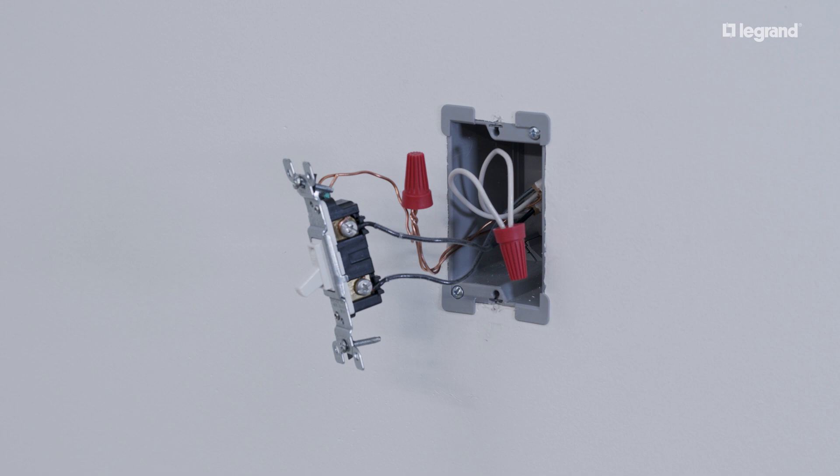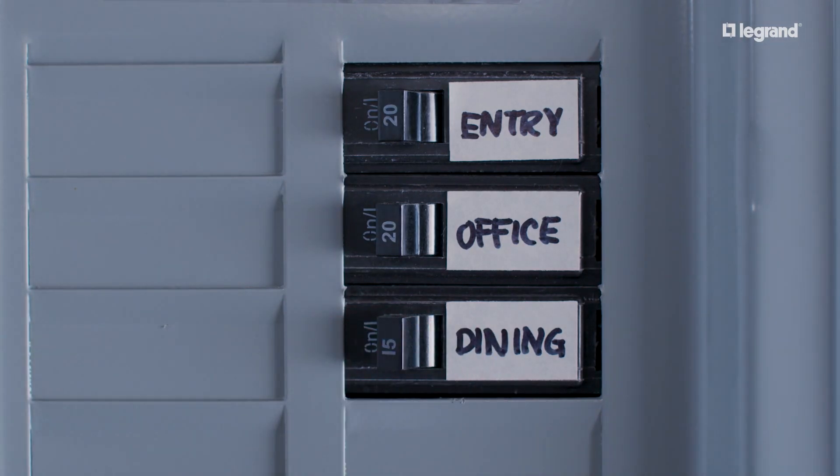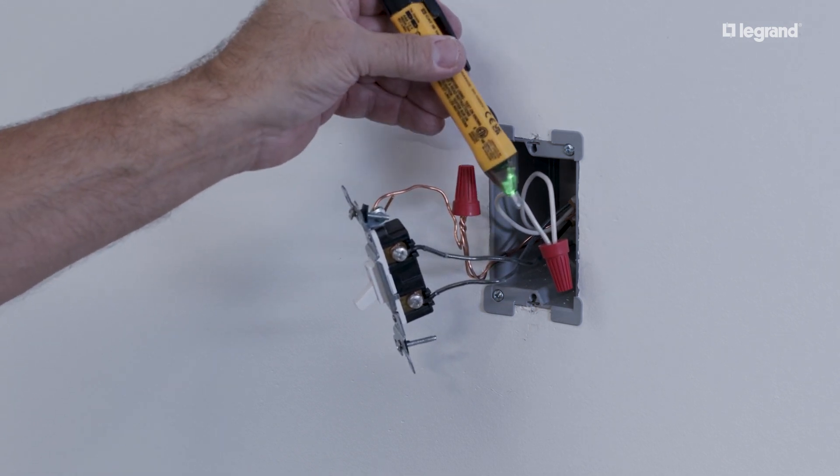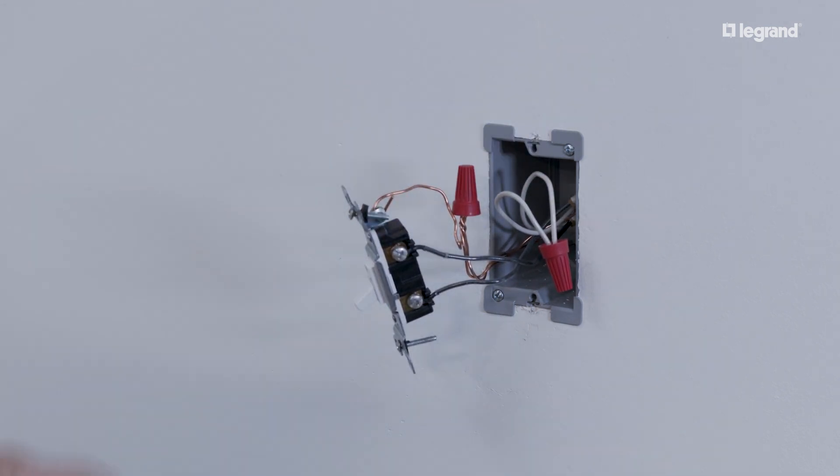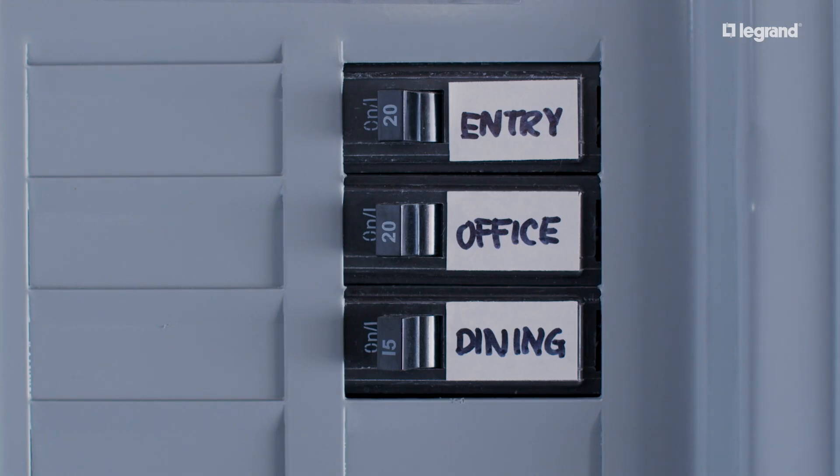If you are unsure which wire is the hot wire, you can determine it with a voltage tester. Turn the power back on at the circuit breaker and use a voltage tester on each wire. The wire with no power is the load wire and the wire with power is your hot wire. Once confirmed which wires are which, ensure power is off at the breaker.